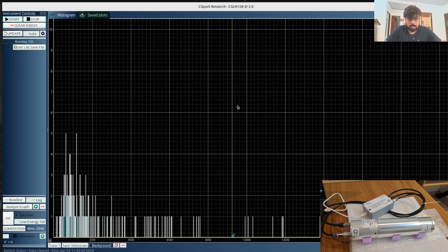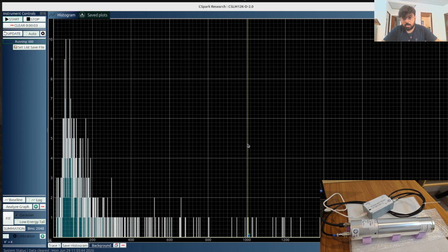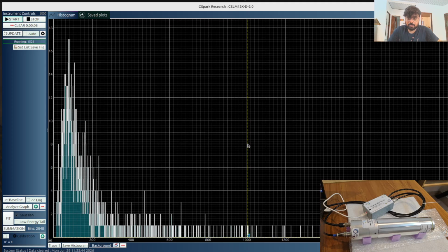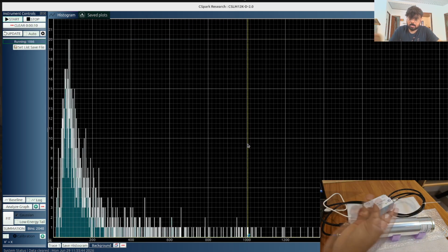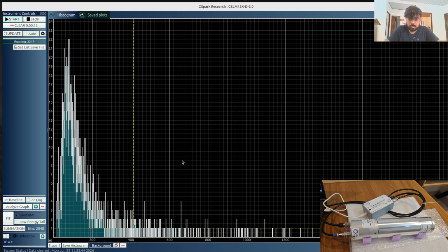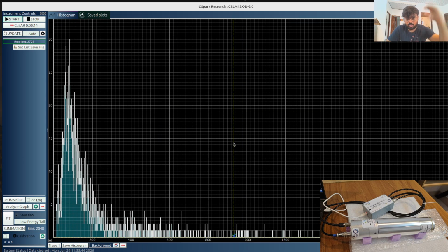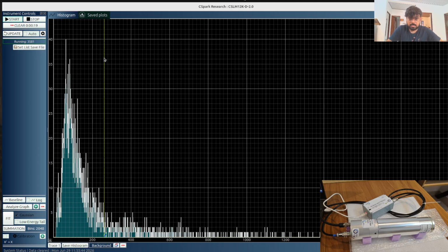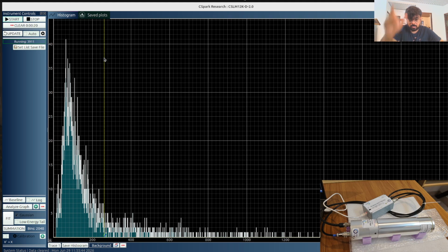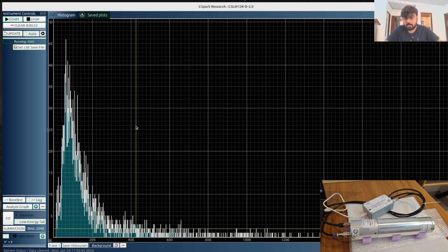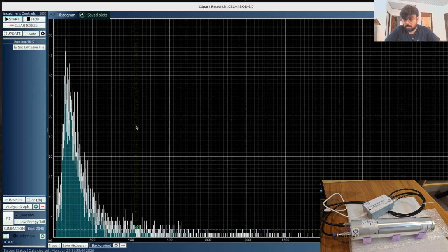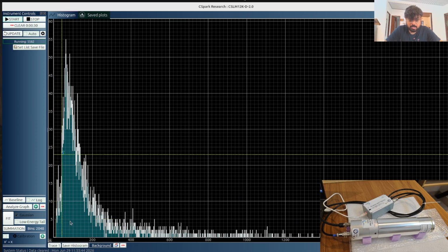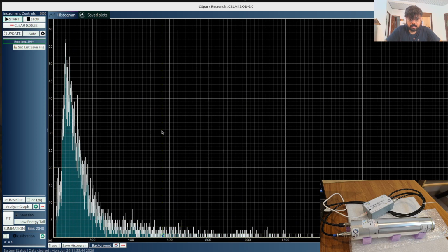Start acquiring. Now this is a list mode 2000 channel MCA. Okay, it's a 2K MCA. So every event is dumped across to the computer, where it is sorted into a histogram. If you want the individual list data, you should set a list save file, which you don't really need. It's just time versus event, time, event, so on. It's a huge column. Then you have to sort it in bins. Since it's a single parameter device, you're not looking at any coincidences or anything. So you just use this direct histogram view.